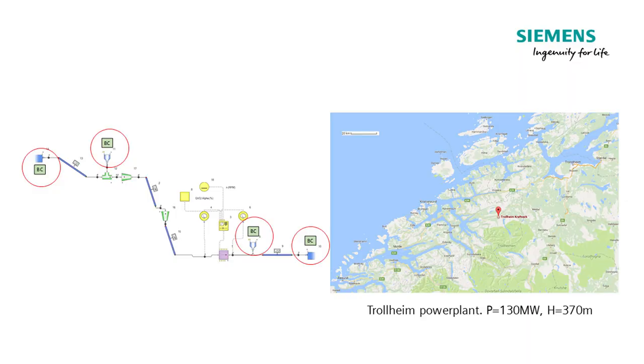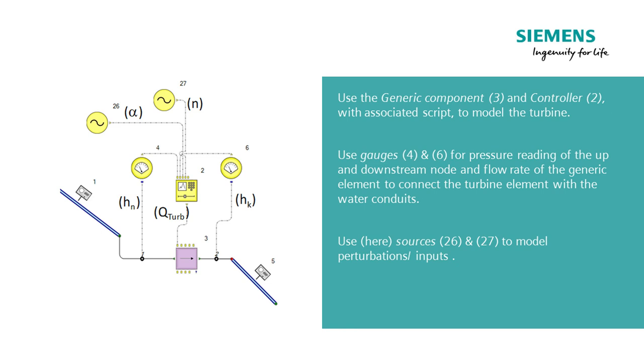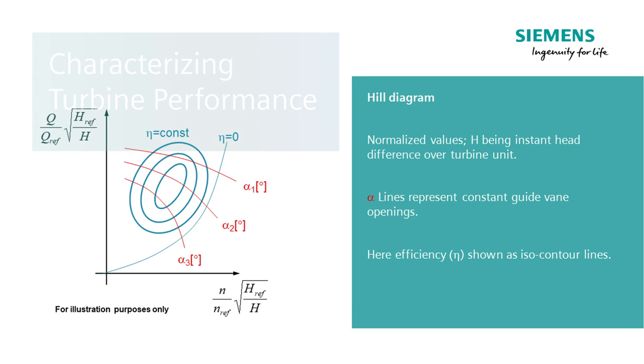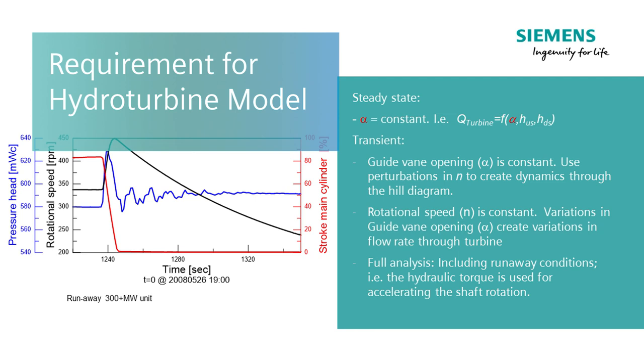The way we can still determine the flows is by using a digital twin. We create a digital twin system model in Simcenter Flowmaster. We measure the input received by the turbine unit in terms of opening rate, which determines the flow rate through the unit. We also measure the pressure in the system very close to the turbine unit, giving us an input and a reference output.